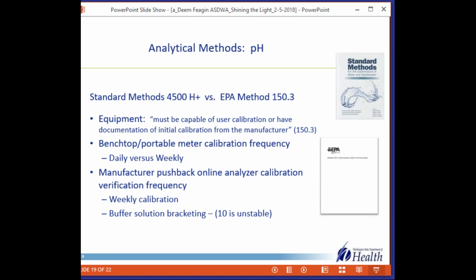So anyway, interesting there. Do you want to have anything else on that one? Yeah. So we also have some seawater reverse osmosis plants in Washington. That's a bit interesting. So pH alkalinity control after that is a big deal, and these instruments that can't be calibrated, the problem is that if you drop it, you break it, the electrode itself goes bad, you're stuck, and you're then inclined to just keep it. Because you can't verify or check it, it's just sitting there. So that seems like not a good way to go. Yes, I think we're agreed on that one.